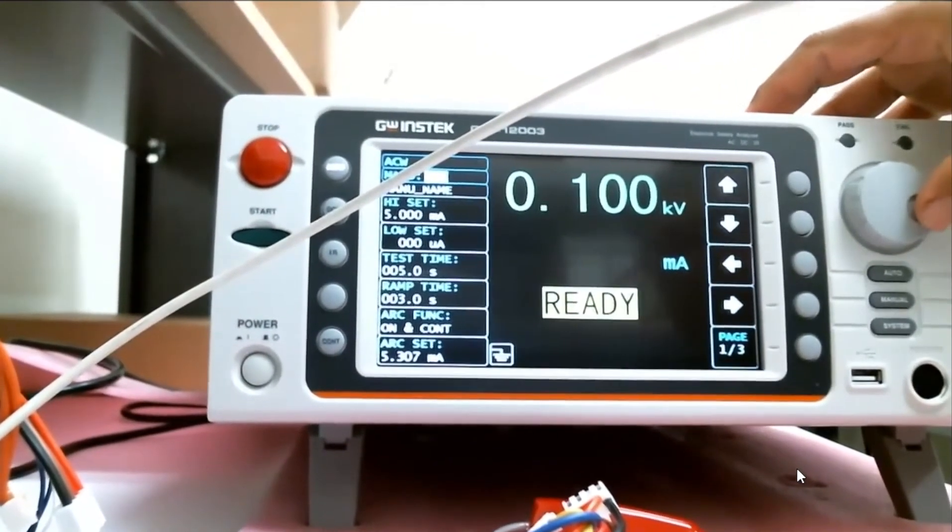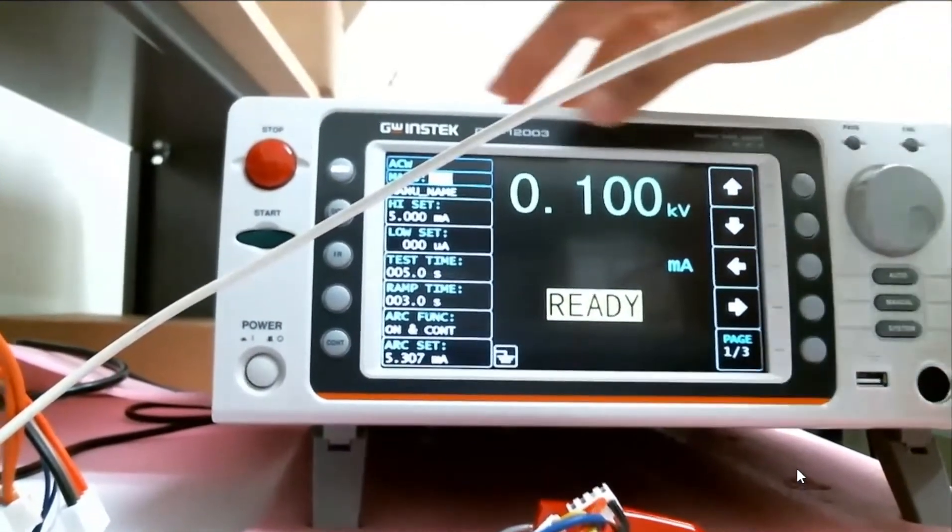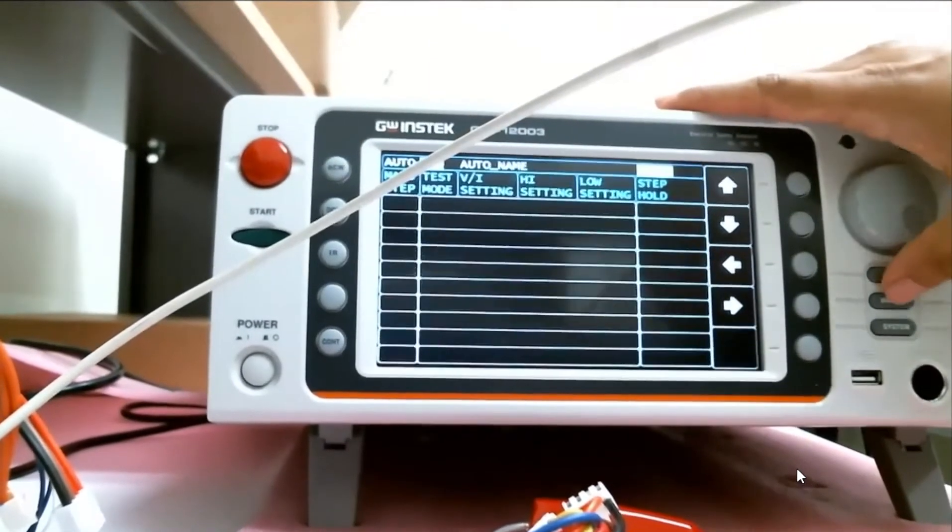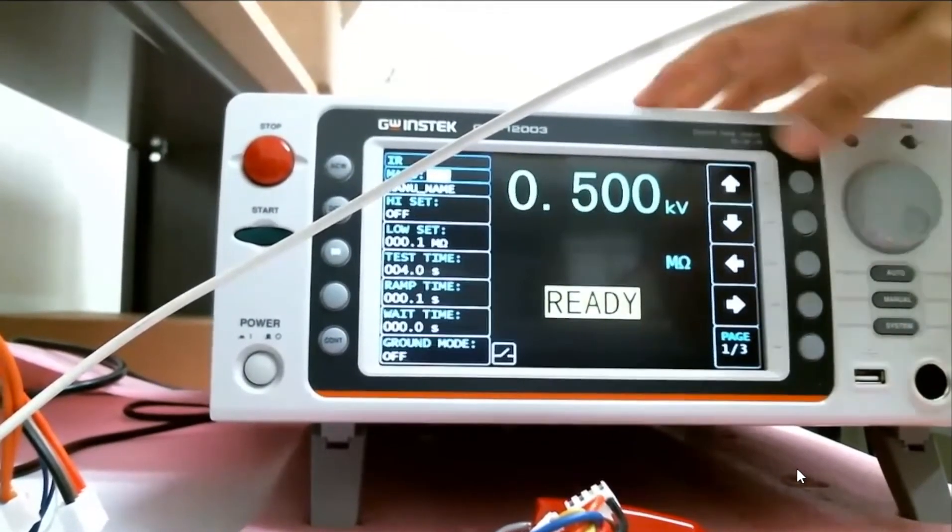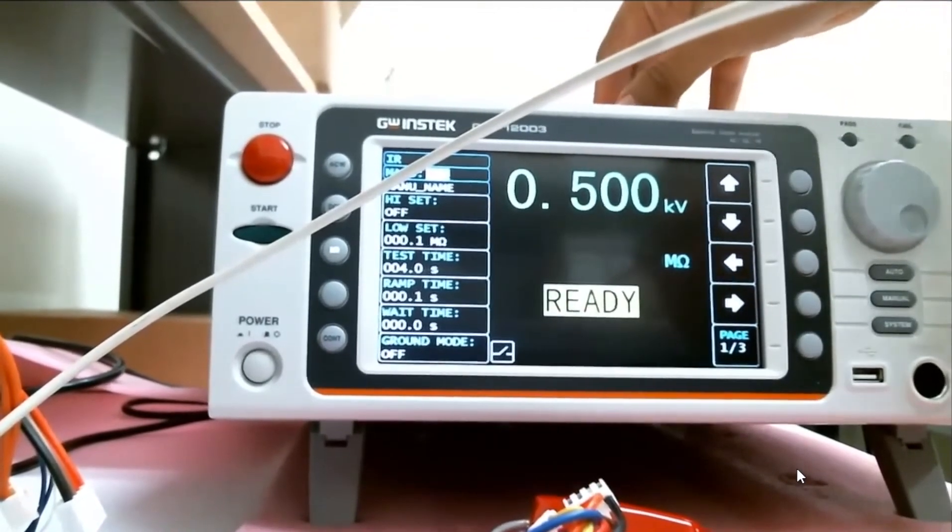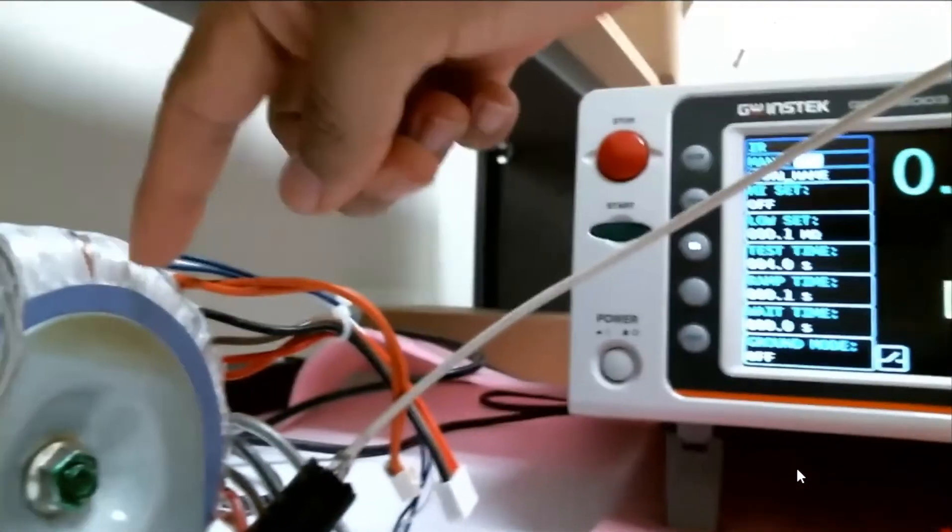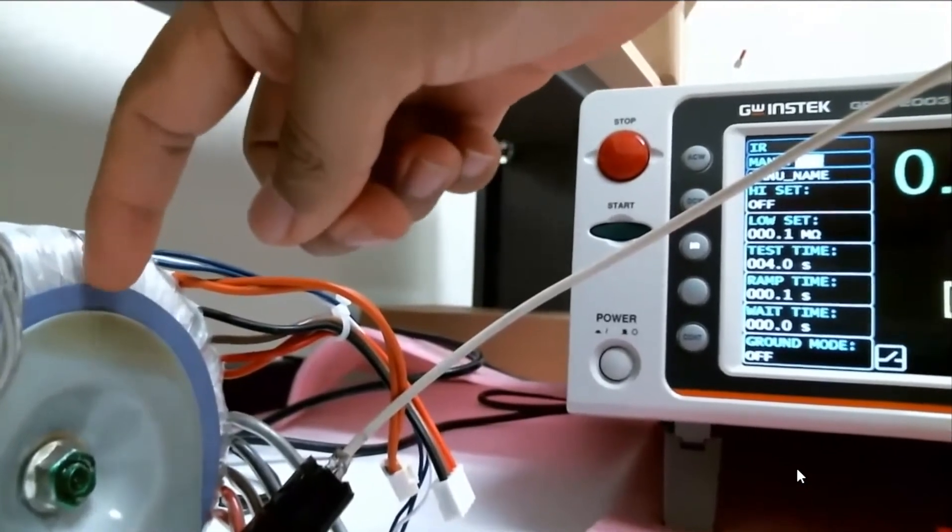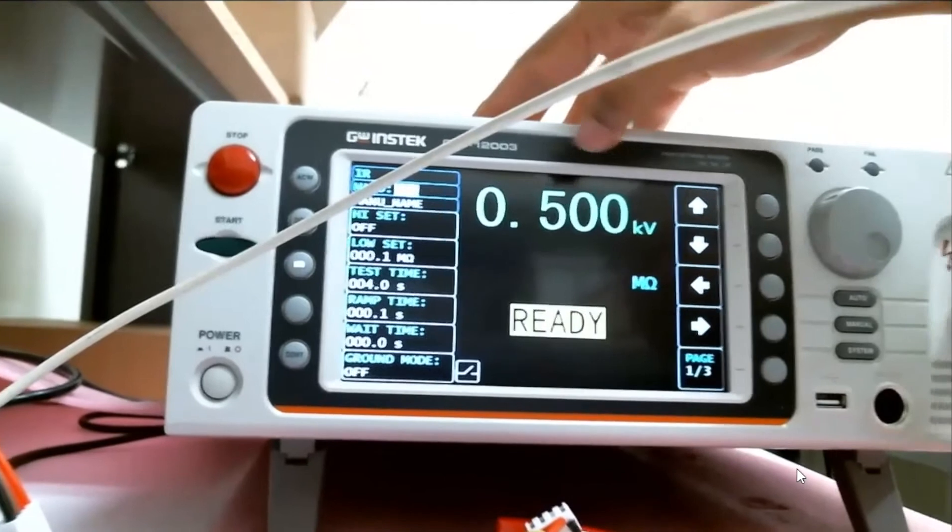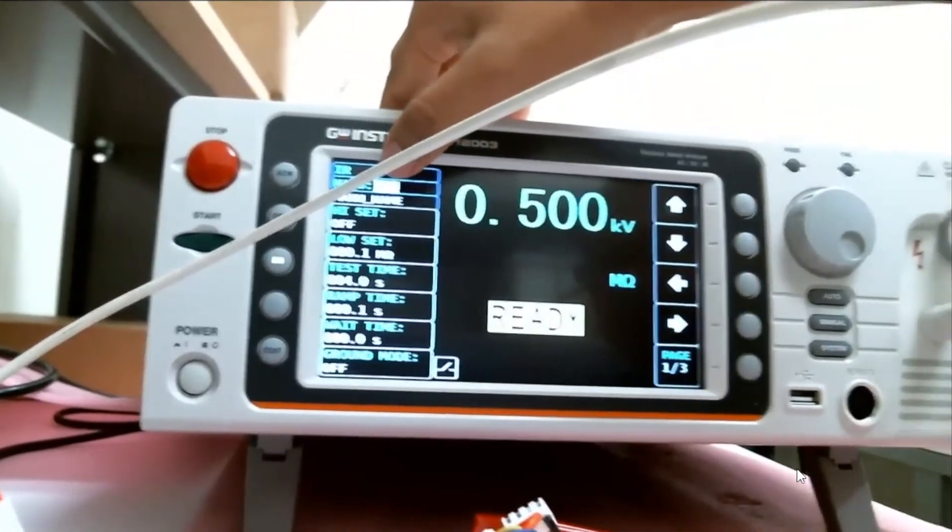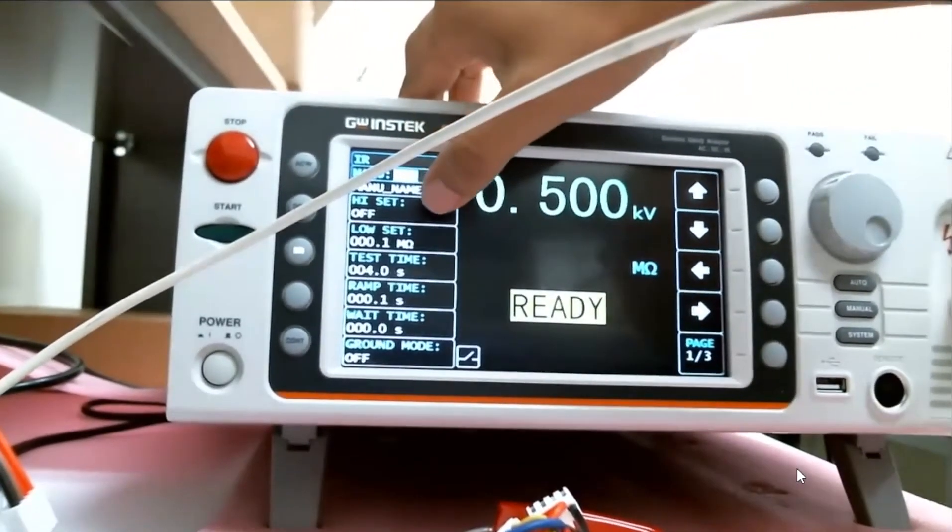The other test I would run here is my IR test. So I'm measuring the insulation resistance of this little thing right here, this isolated piece of rubber, at 500 volts. There is no high set in this case, there is a low set. My test time is 4 seconds.